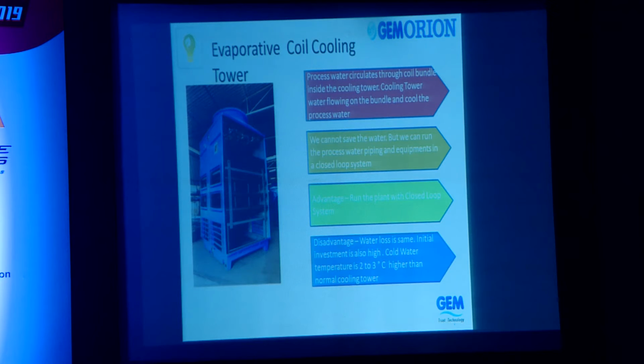The advantages and disadvantages: the system can run in closed loop, so machine life doesn't get affected, no scaling, no deterioration in capacity, so it is maintained well. The disadvantage is that the evaporation loss is directly proportional to the heat load you are removing, because the cooling tower works on the principle of latent heat. Once you evaporate, you remove the heat, so it is directly proportional to the heat load. So you cannot save water, but you can avoid the problem of scaling or choking in your mother machine. Mother machines are more expensive, so you can protect that machine. Here the water loss is the same, but the initial investment is high.